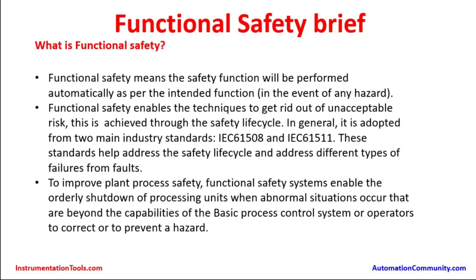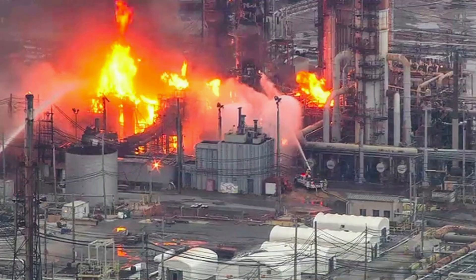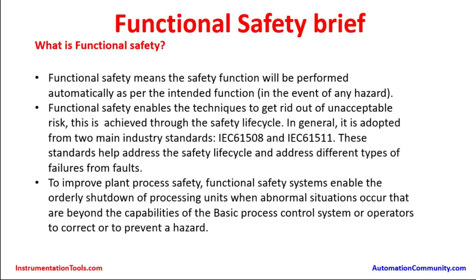Functional safety means the safety function will be performed automatically as per the intended function in the event of any hazard happening. Functional safety enables the techniques to get rid of unacceptable risk. This is achieved through the safety life cycle, and in general it is adapted from two main industrial standards: IEC 61508 and IEC 61511.